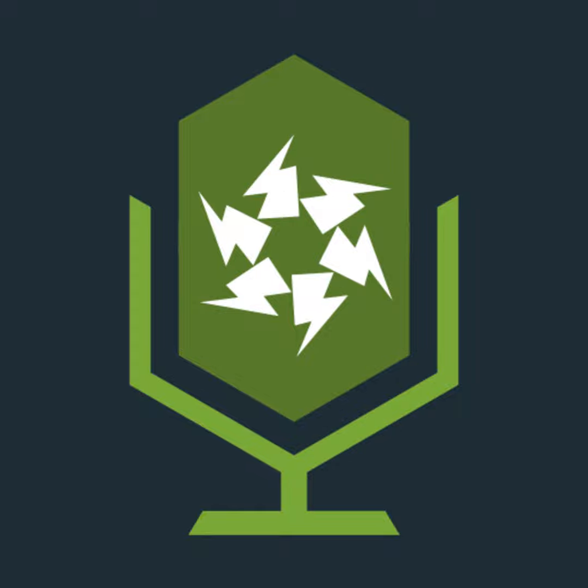This is a good one. 524.2.2. The total harmonic content due to triplen harmonics. That's the third harmonic, which we touched on previously. If it's more than 33% of the fundamental line, so that's the first frequency, so you've got your first AC wave, and then obviously in that one wave, the third harmonic, there are 3 of them. And if their cumulative value of voltage is more than 33% of the voltage in the fundamental, then we'll need to increase the size of the cable accordingly.